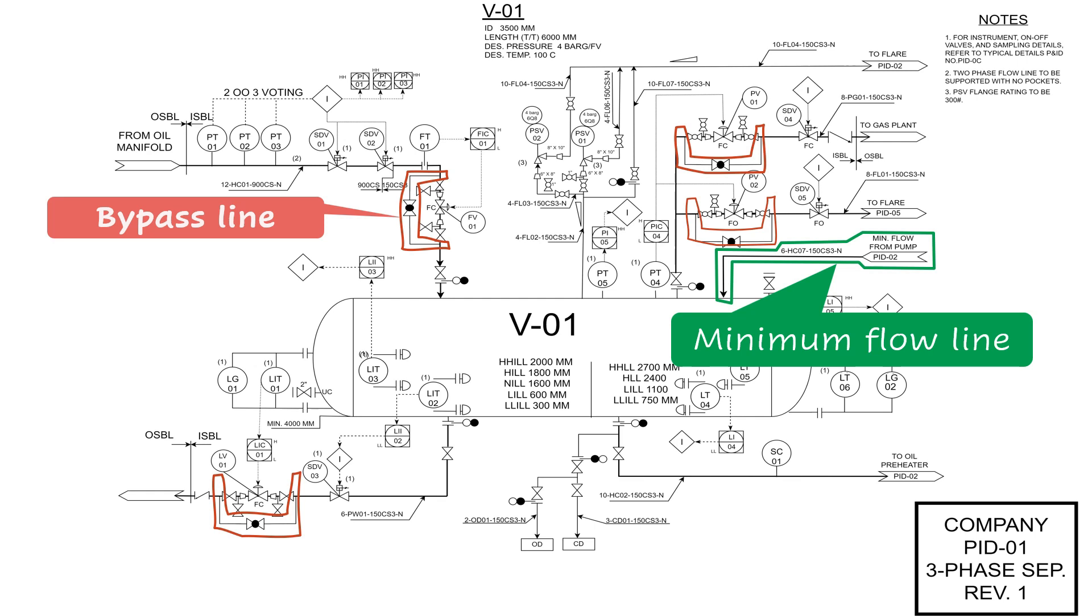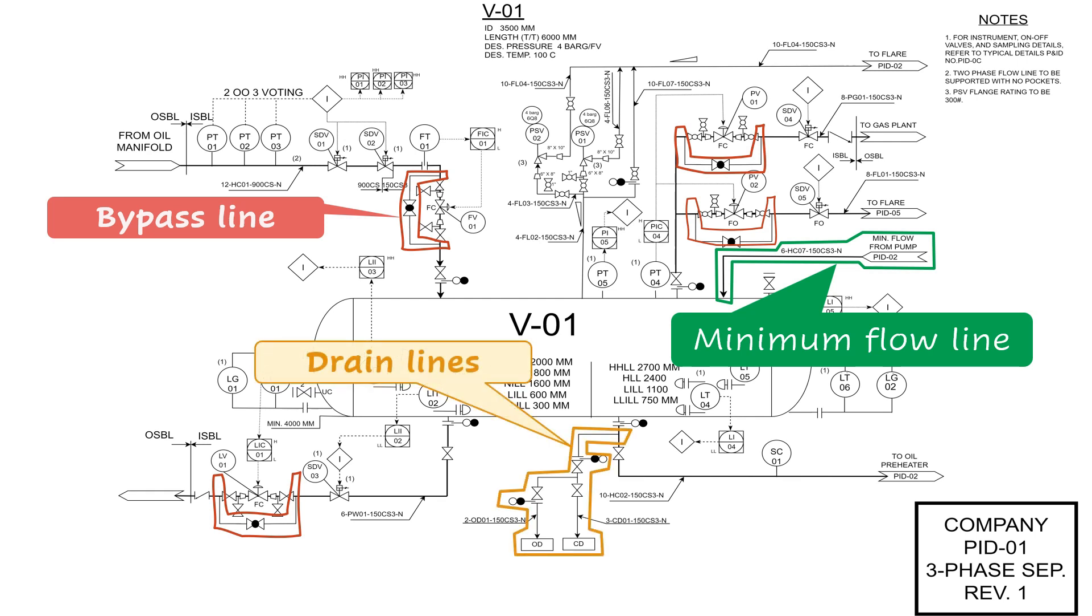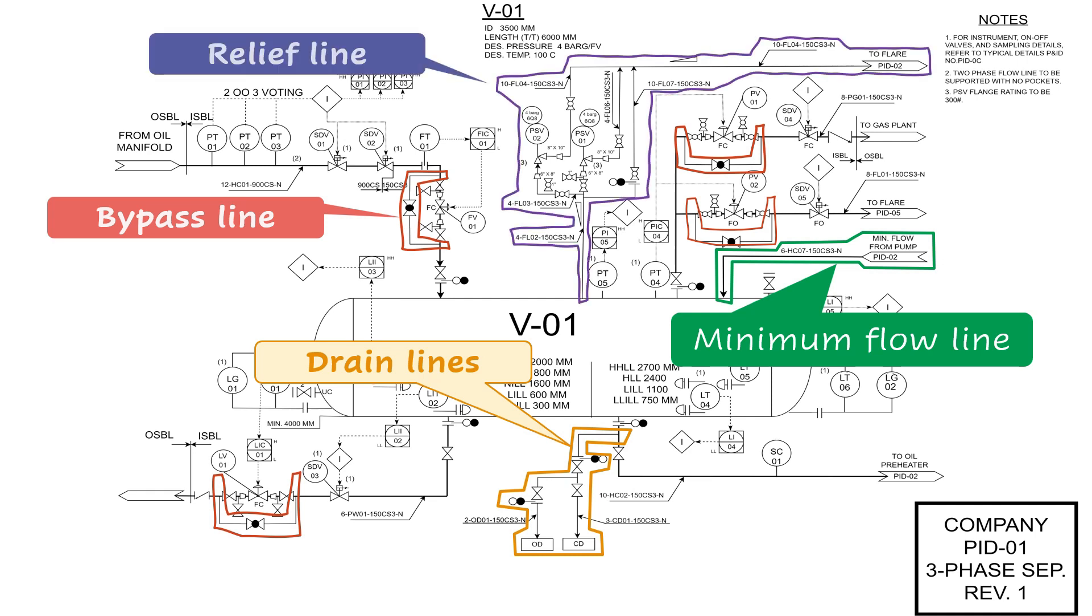For effluent lines, all lines going to closed drain system, or to open drain system, or to flare, should be shown on the P&IDs. These systems are typically not shown on the PFDs.